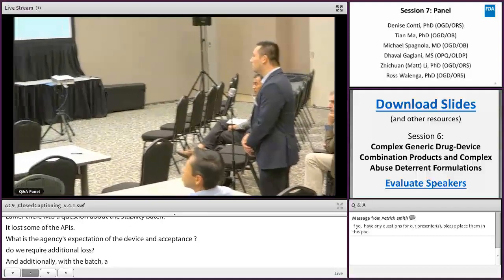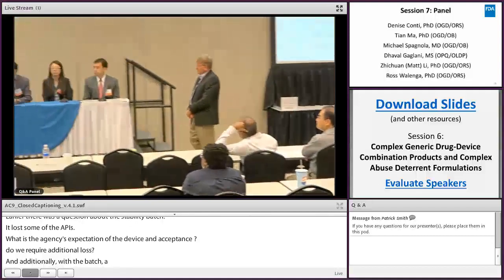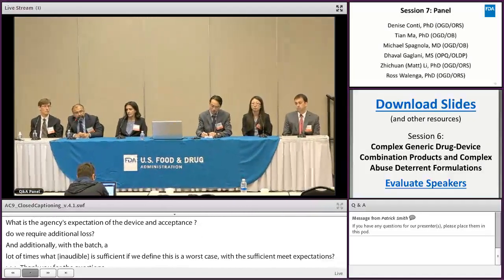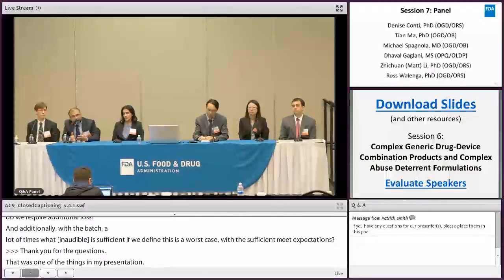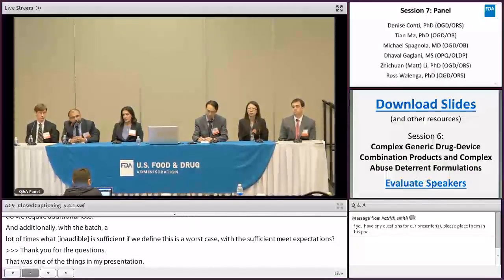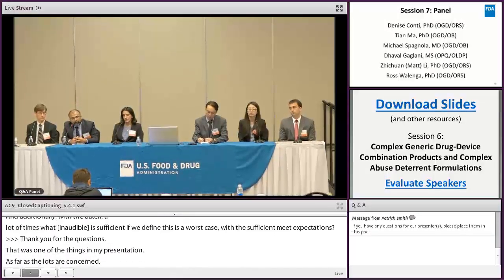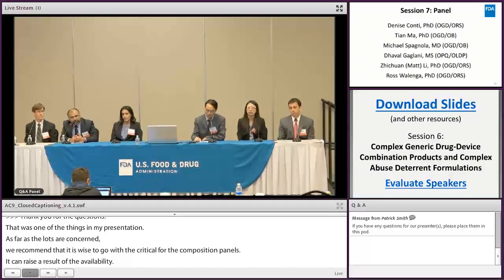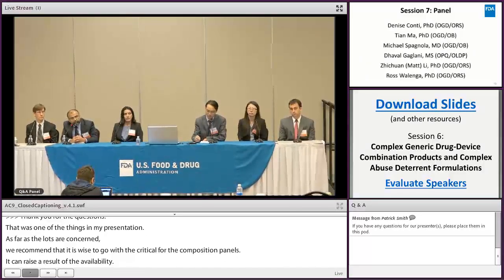Thank you for the question. I think that was one of the things in my presentation. As far as the lots are concerned, we do recommend that at least for the device, since it's a critical constituent part for the combination product, and it can result in a lot of variability, the registration batches not only be manufactured using 3 API lots, but also 3 device lots, including, if you can, especially for an excipient which plays a critical role for dry powder inhalers, for example, you want to ensure that you also include 3 lots of lactose for your product for the registration batch.